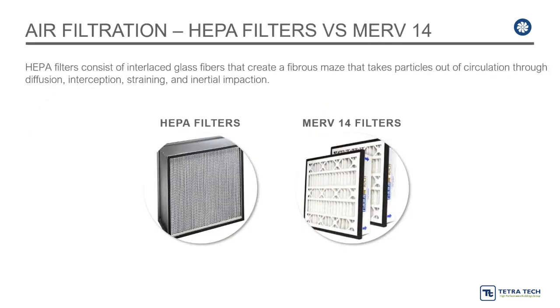While the HEPA filter is the only filter that can capture these small virus particles, we're primarily concerned with particles that have moisture and proteins. These tend to be slightly larger, 0.3 microns, and can be effectively captured by commercially available MERV 14 filters. It's not easy to change out air handling systems to accommodate the large pressure drop of HEPA filters.